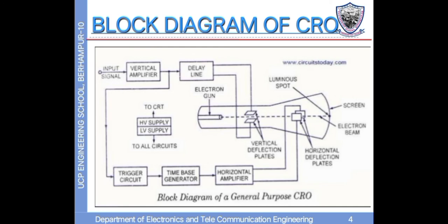The output of the vertical amplifier is given as input to the delay line. We know that the input signal is applied to both the horizontal and vertical deflection plates. Before reaching the horizontal deflection, the signal passes through different blocks such as the trigger circuit, time base generator, and horizontal amplifier. Thus, a small delay occurs and the signal reaches the vertical deflection plates earlier, which causes disturbance of the signal on the screen.